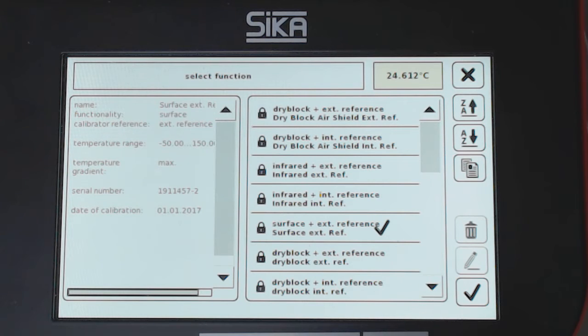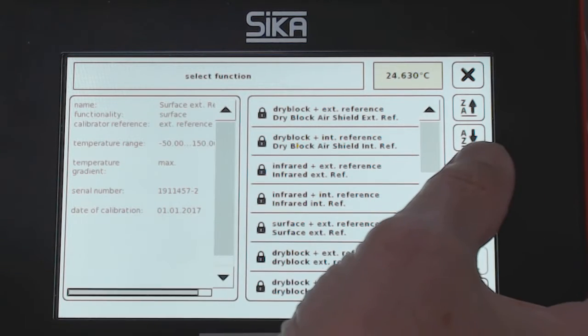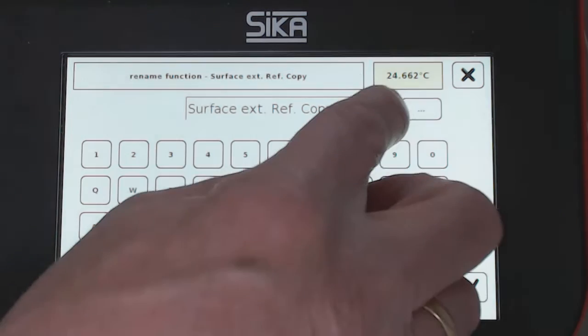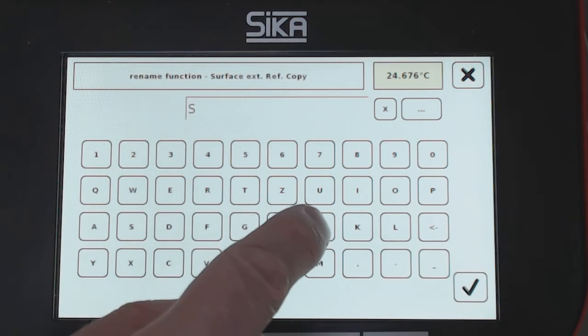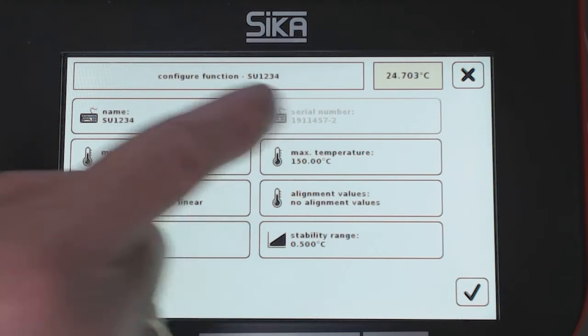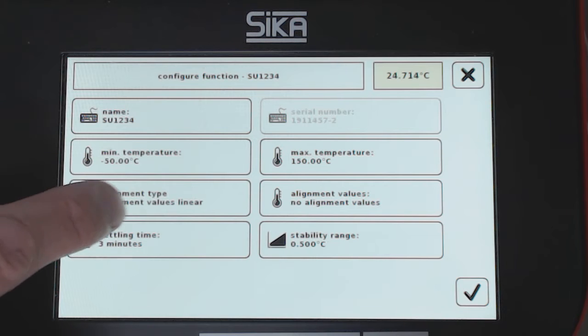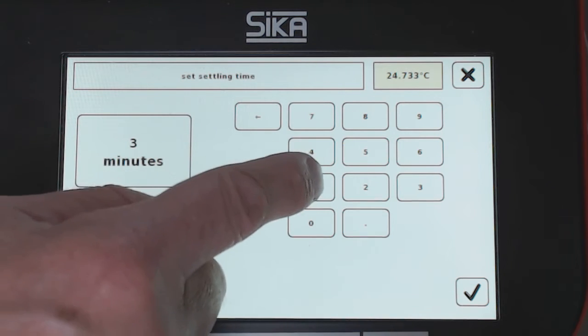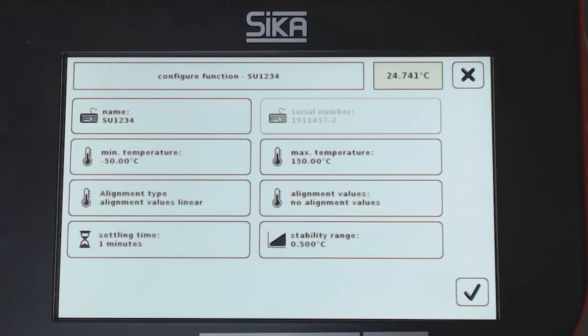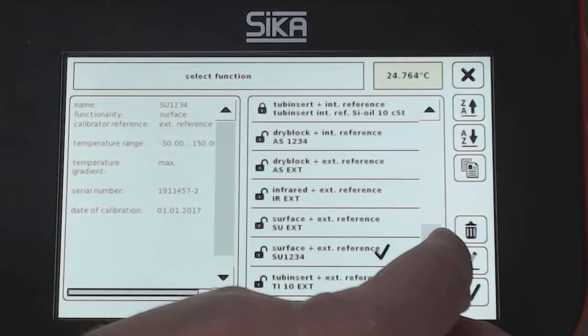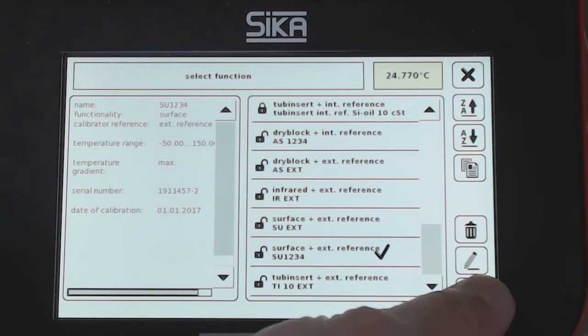If I like to make some modifications, I make a copy of this locked closed function and open it. I can give a name — SU1234. The temperature range is from minus 50 up to 150. The alignment type is linear with no alignment values. The settling time I change from 3 minutes to 1 minute, and I confirm. The stability range is the default value of 0.5 degrees Celsius. I confirm. I can check in the list — yes, this is my function. The function is selected. I confirm.